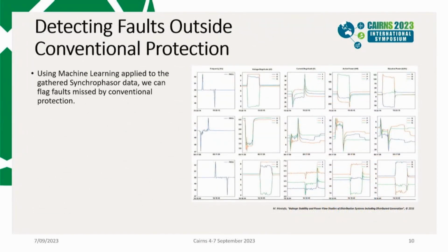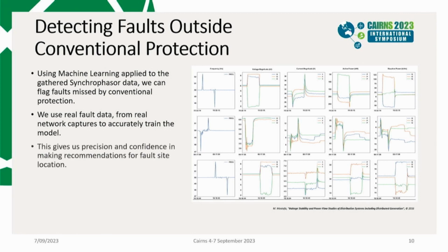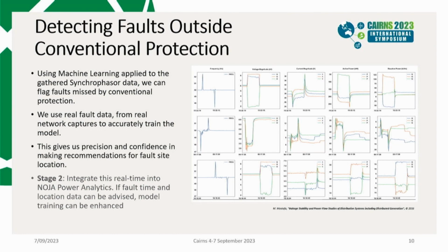We also managed to detect faults that would normally be missed by conventional protection, and again, this is another case of using machine learning to process that synchrophasor data. The best way to do this is if you can correlate the information from your existing fault data with the data that you gather from the PMUs in order to train your own model to detect these various cases on the distribution network. And so it gives us precision and confidence in making recommendations for fault site locations as well. So it provides additional information that you would normally not get from conventional implementation.